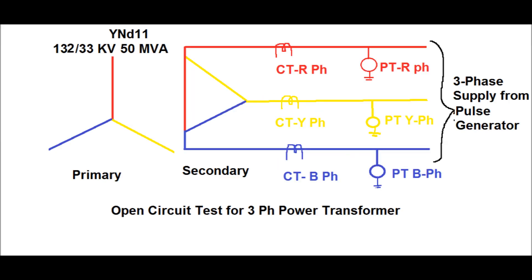The arrangement for the open circuit test of a three-phase power transformer is shown in this diagram. The primary is Y-connected and the secondary or LV side is delta-connected. The primary is voltage class 132 kV and secondary or LV side is 33 kV voltage class. The transformer rating is 50 MVA, and three-phase supply is given from a three-phase pulse generator.